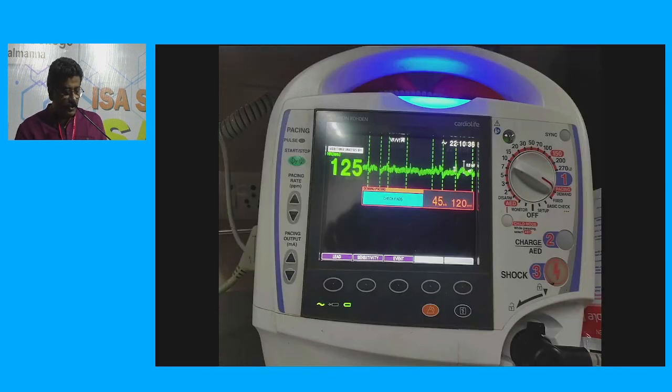On the left side, where you can see the pacing rate, you can either increase or decrease it. Then increase the current, which is shown below. You increase the current until you get a pacing for each P, so that there is a QRS.